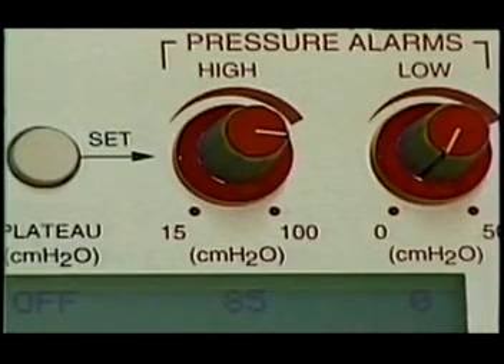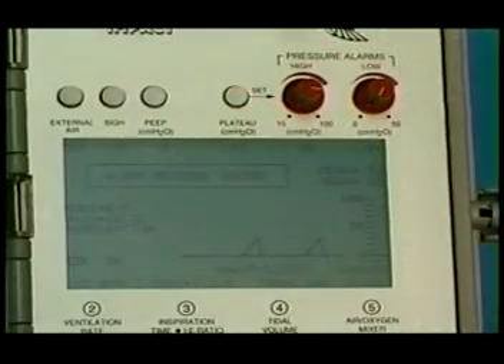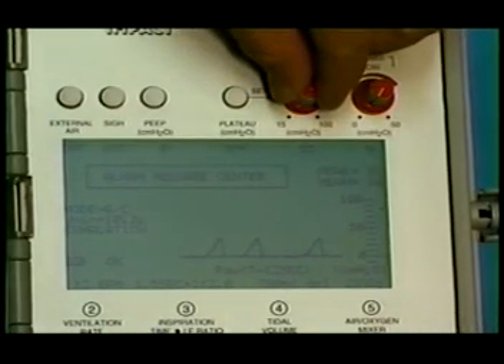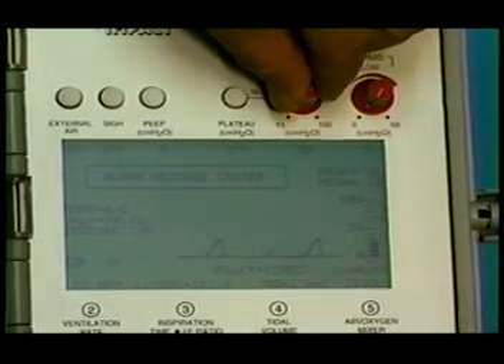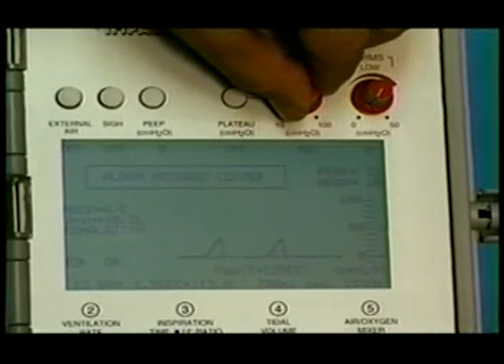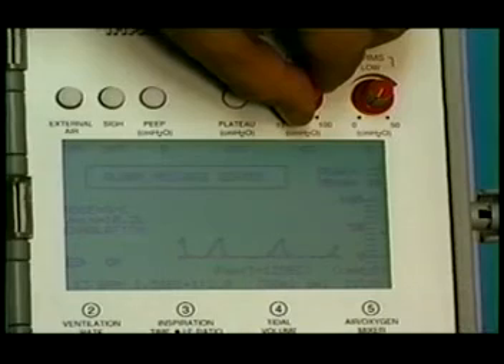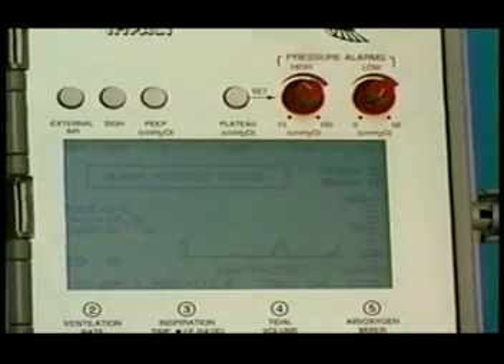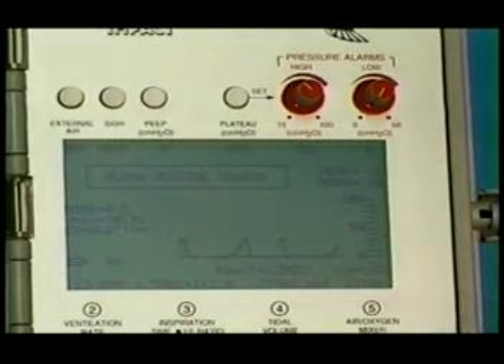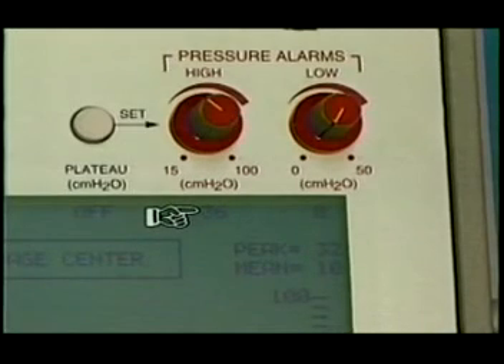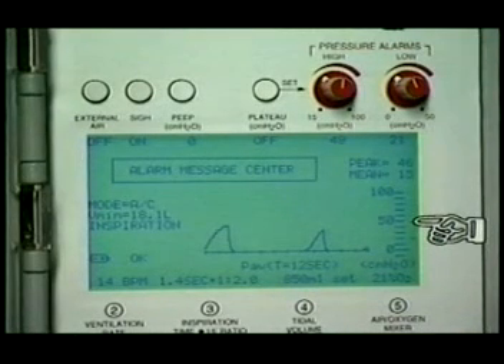The high-pressure alarm peak inspiratory pressure relief control sets a threshold value for the high-pressure alarm and peak inspiratory pressure relief. Its range is 15 to 100 centimeters of water based on the control position, and activates when inspiratory pressure exceeds the set point at any time during 4 consecutive ventilations. Its value is displayed in the LCD beneath this control. The high airway pressure alarm set point indicator shows the current setting of the high pressure alarm control. It is displayed adjacent to the digital bar graph.